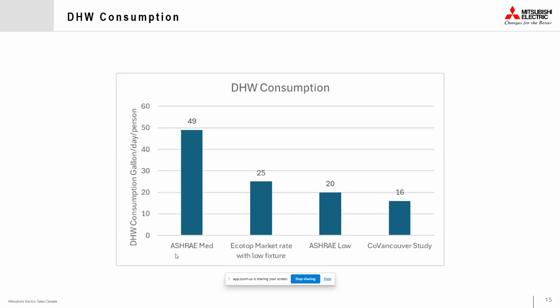In terms of different criteria we have for domestic hot water consumption per person, the ASHRAE medium says that for the medium range, per person per day, you will require 49 gallons. Ecotope, that's an online tool available, recommends if you have low fixtures, like 1.4 or 1.5 GPM for your faucet and shower heads, then you can use 25 gallons per day per person. And ASHRAE low criteria is based on if you have all those energy saving measures, then you can use the criteria of 20 gallons per day. So you can see how much the gallons per day varies because of different criteria.